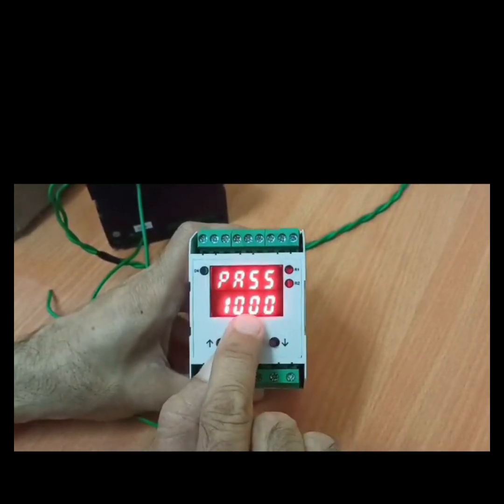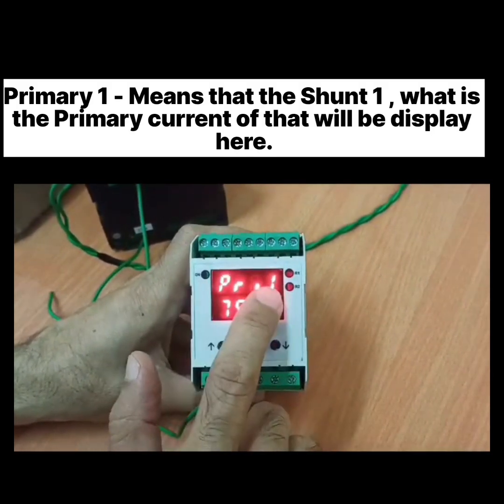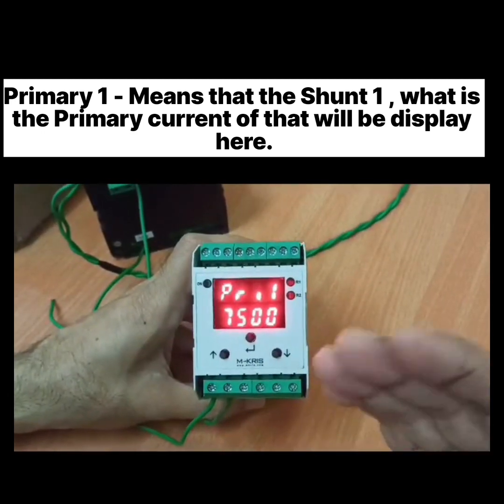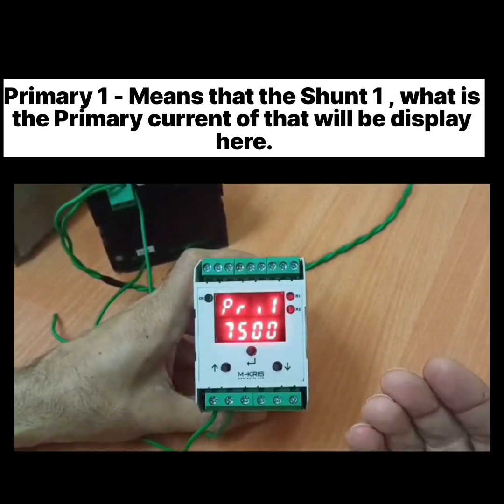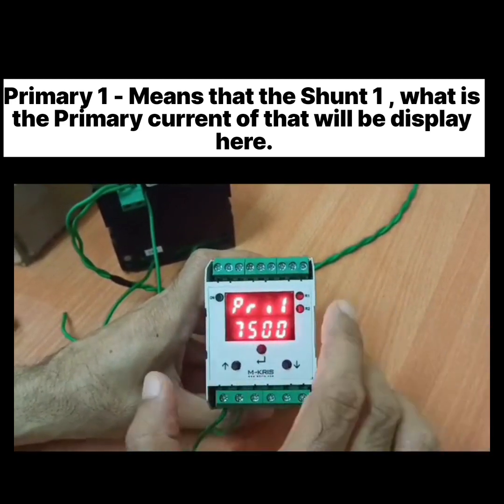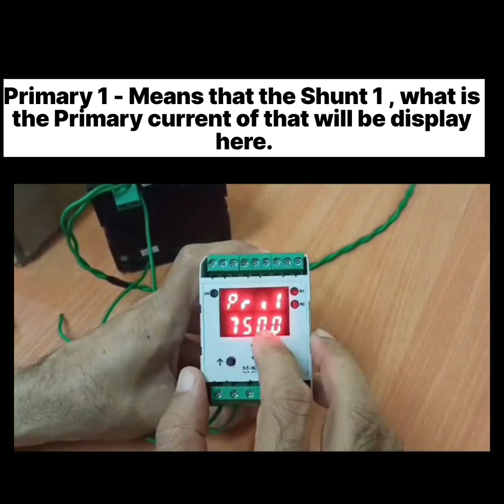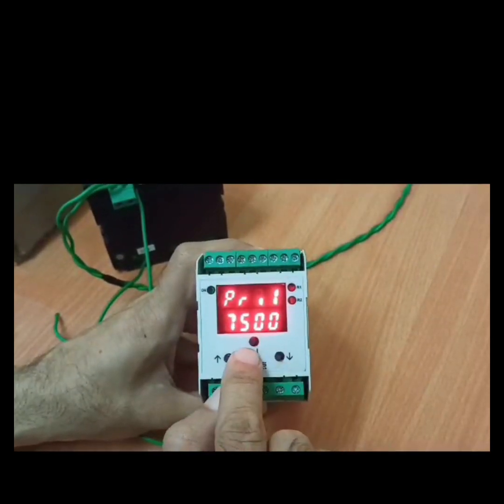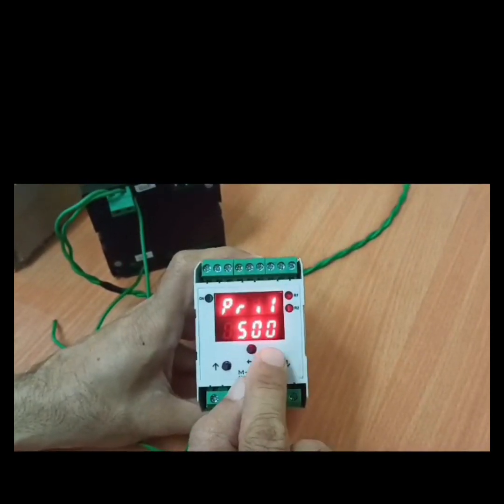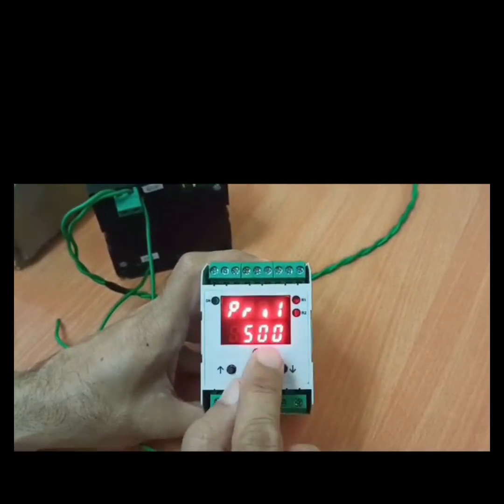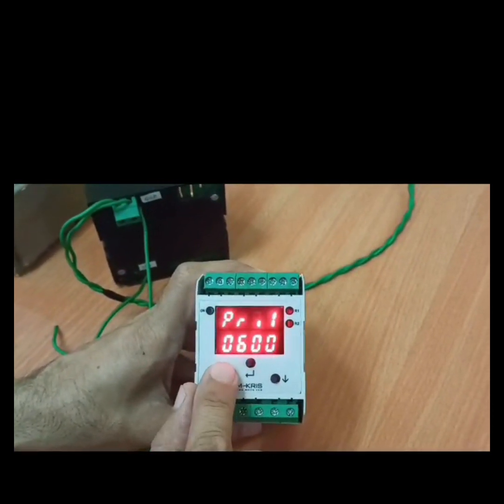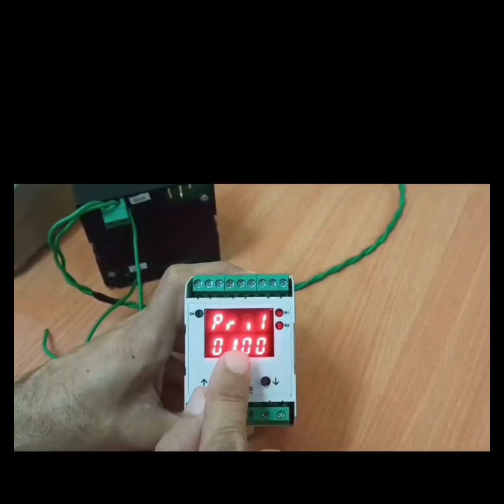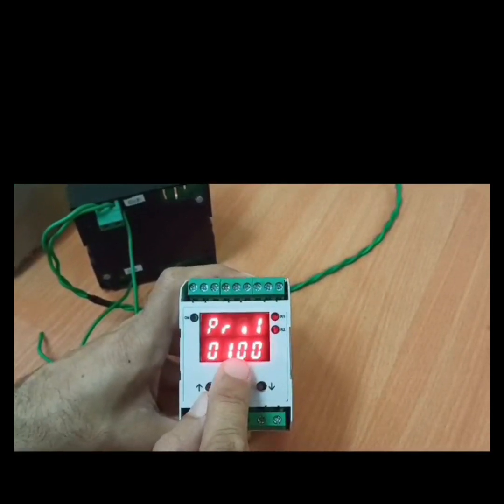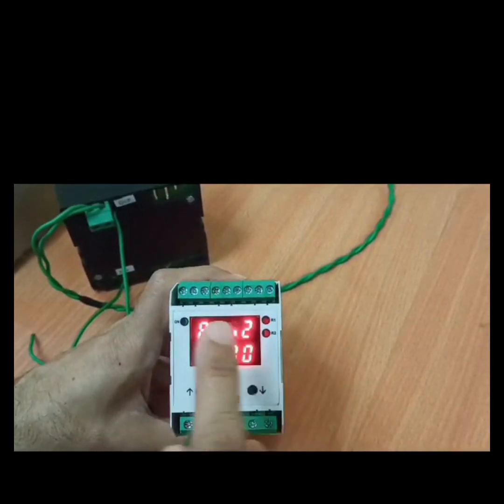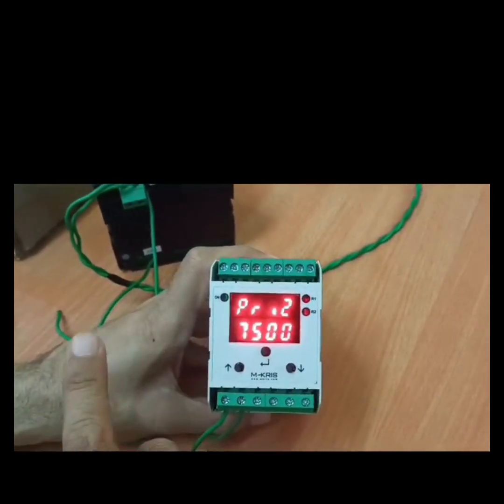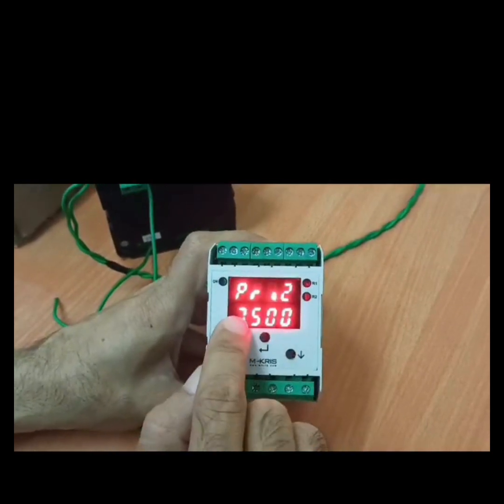So these three buttons are used for the menu. Now this is the primary one, which means that for shunt 1, the primary current of that will be fed here. So let's say if that is a 100 ampere shunt, we can change the setting here. Again we press the first button, we can bring it down to 0. Then the second digit we can take to 1, and this way we have set the shunt of channel 1 to 100 ampere. Similarly, this can be changed.